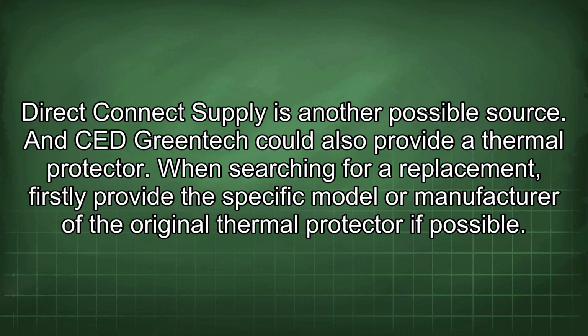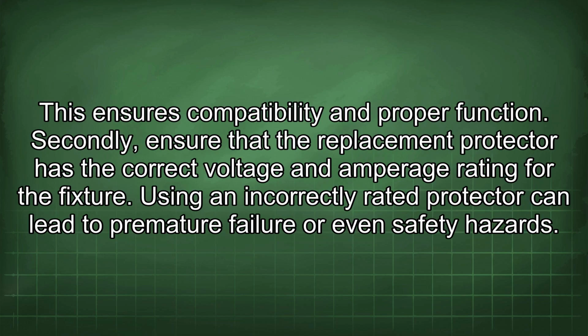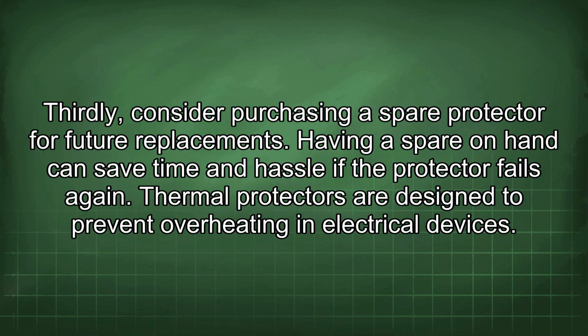When searching for a replacement, firstly provide the specific model or manufacturer of the original thermal protector if possible. This ensures compatibility and proper function. Secondly, ensure that the replacement protector has the correct voltage and amperage rating for the fixture. Using an incorrectly rated protector can lead to premature failure or even safety hazards. Thirdly, consider purchasing a spare protector for future replacements. Having a spare on hand can save time and hassle if the protector fails again.